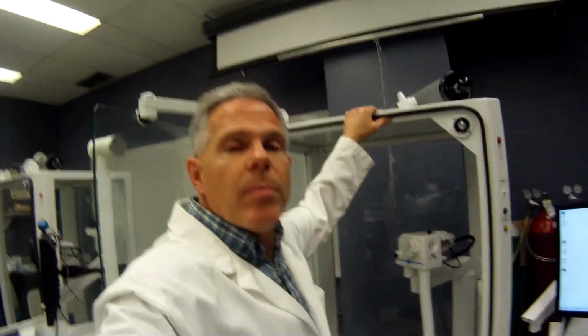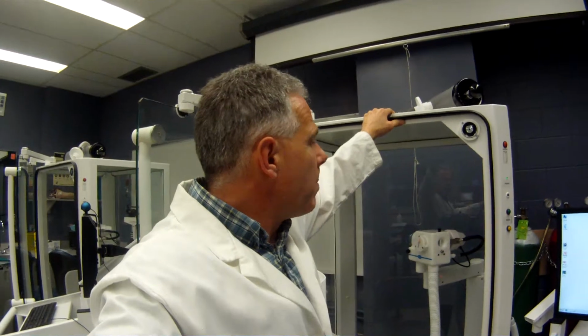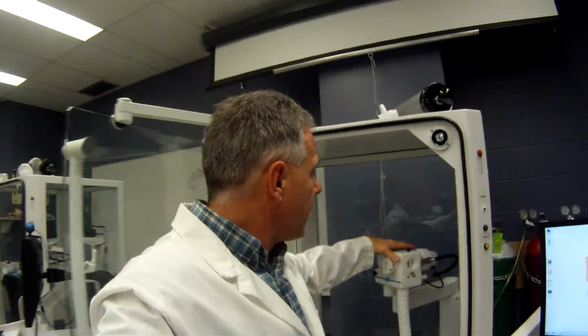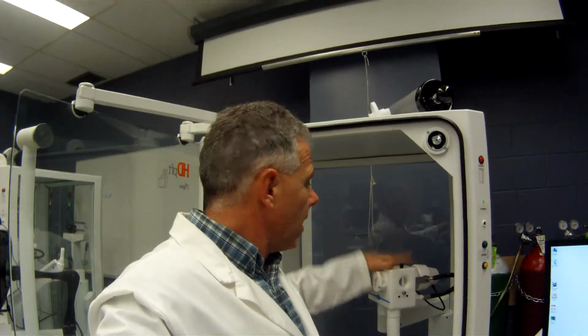This unit is a little bit different than the portable units, even though it's operating the same software, okay? Because this one's attached to the body box and it has the capability of doing a nitrogen washout, a DLCO, single breath nitrogen washout, and the body box here, the plethysmography. So that's the key things about this unit. I'm going to show you how to do a calibration here in just a minute.